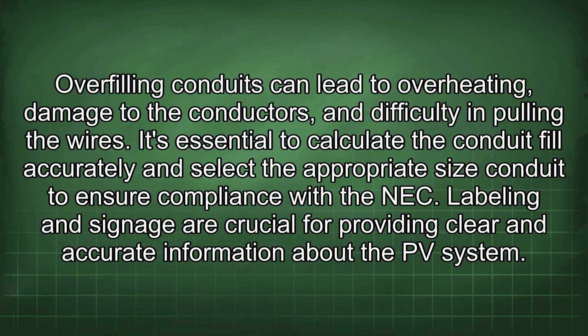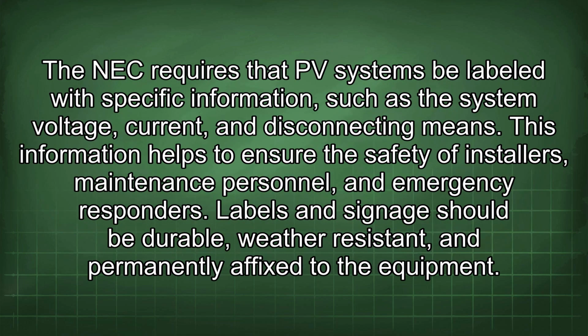Labeling and signage are crucial for providing clear and accurate information about the PV system. The NEC requires that PV systems be labeled with specific information, such as the system voltage, current, and disconnecting means. This information helps to ensure the safety of installers, maintenance personnel, and emergency responders. Labels and signage should be durable, weather-resistant, and permanently affixed to the equipment.